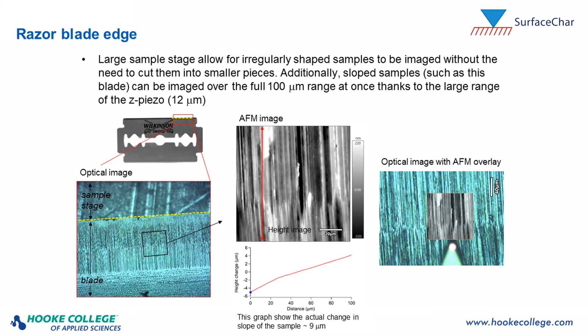And the reason that matters is, if we can see here, the slope of that edge actually is about 9 microns. In a small sample instrument that has a Z range of only 5 microns, you would not be able to image that whole slope because you'd run out of Z range. But having this large sample instrument with the large Z range as part of it enables you to measure this entire range. And so not only do you get the full range, but now you can get a very high resolution image of the structure and morphology on this razor blade as shown here. This is our AFM topography image, and they can overlay that even onto the optical, so you can get a nice compare and contrast that way.